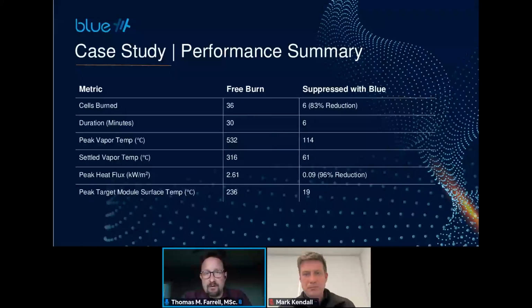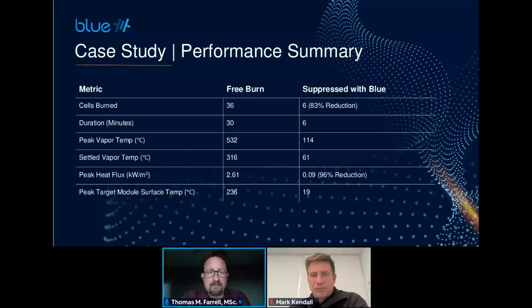The suppression test was over in a fifth of the time of the free burn, which means you have time to ventilate, you have time for the atmosphere to carry some of those gases away and reduce the concentration of those gases near populated centers. There was a really dramatic decrease in the peak vapor temperature, but what's not captured there is the duration. During the actual burn, it's half an hour versus 6 minutes, but it's half an hour at 500 degrees Celsius versus 6 minutes at 114. It's a pretty big difference in terms of the thermal load in the atmosphere that it's going into.